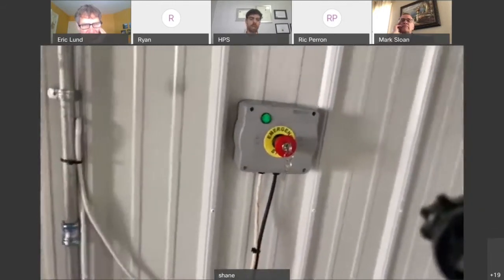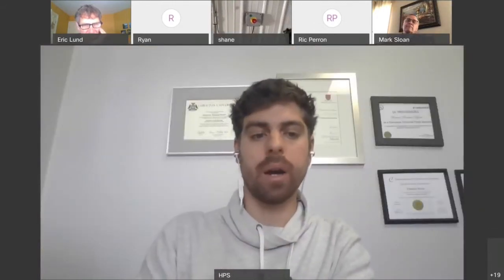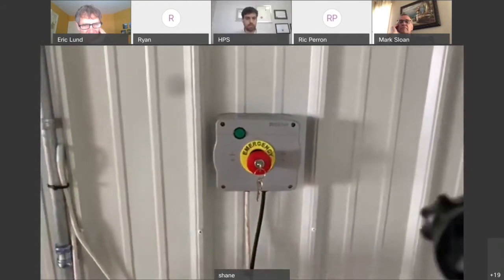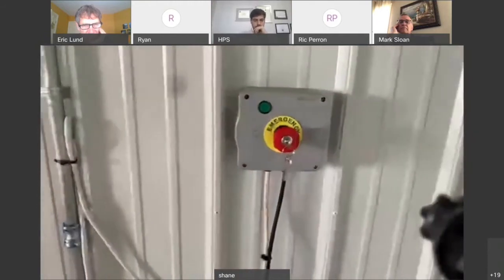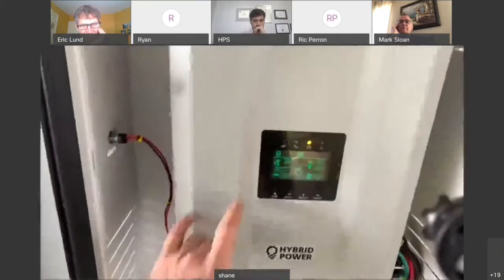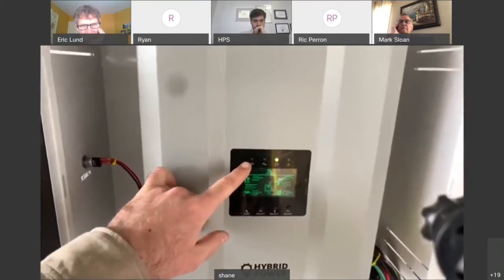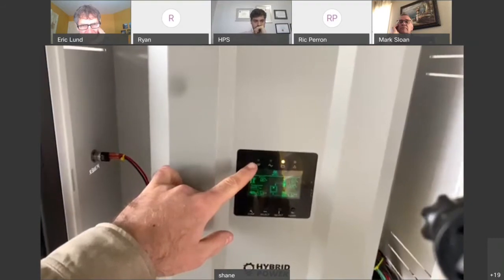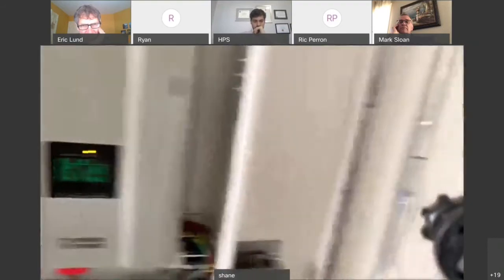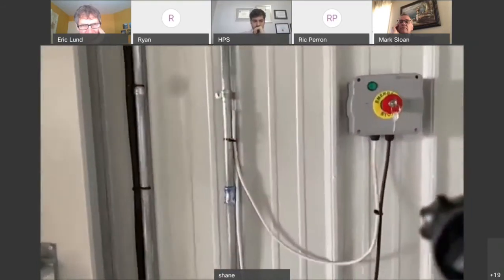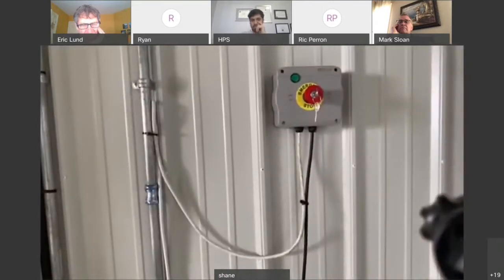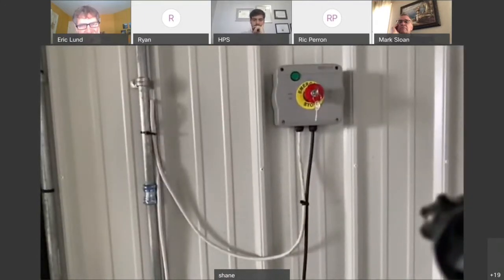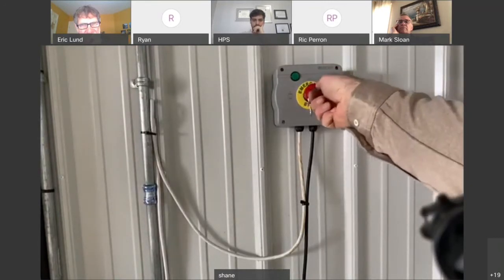They could also be hitting that red button. So we lost our input. We lost our 24 volt transformer, which feeds all of our rapid shutdown modules. Then we come here, and you can see that we've lost our PV input. So now it is safe to work on the system if you're going to be cutting a hole through the roof. This is basically great if you're just doing a grid tie system or a hybrid system that's not islanding.